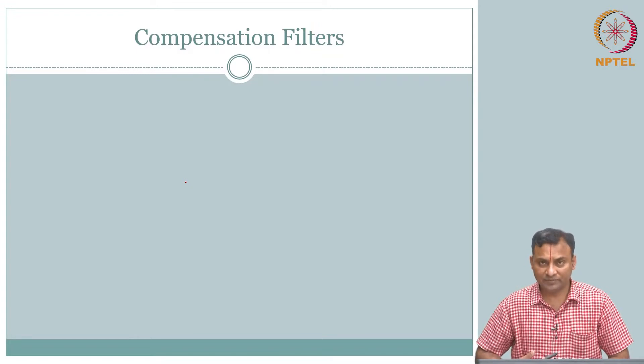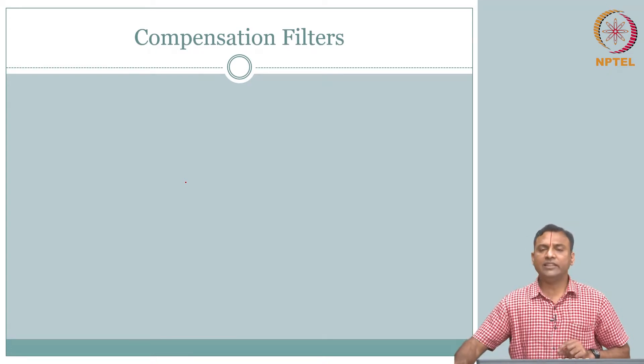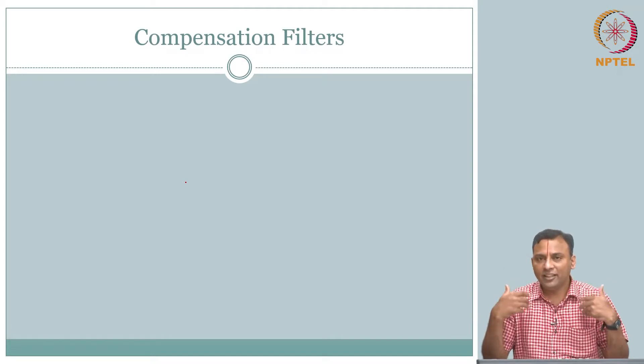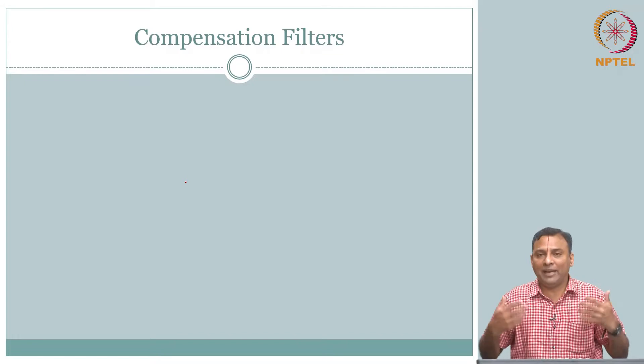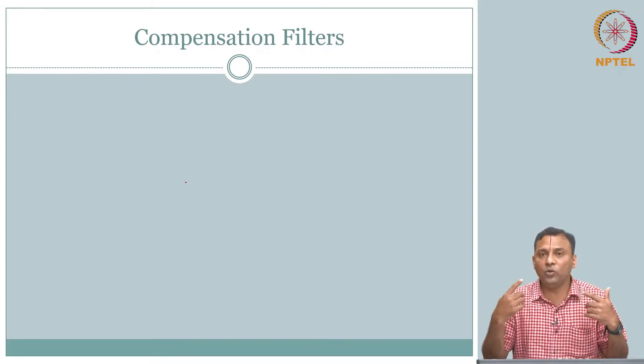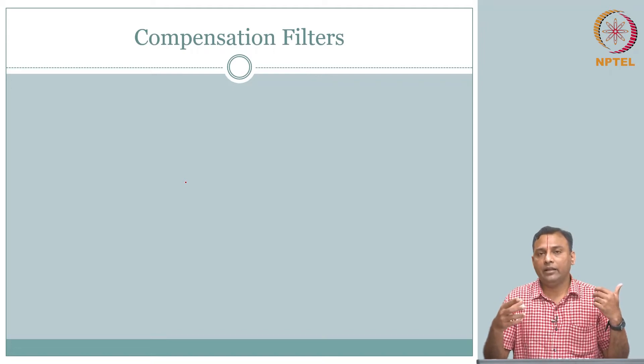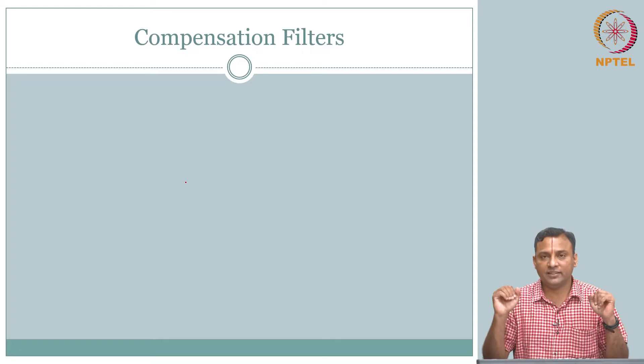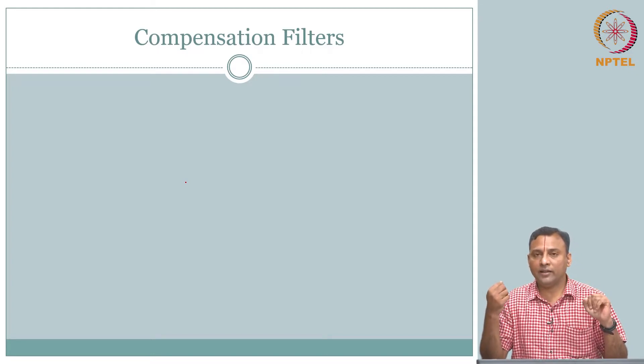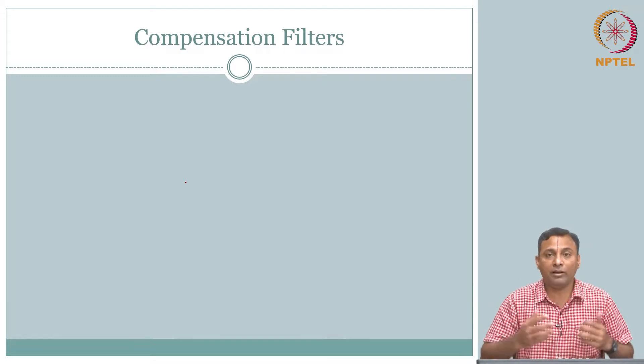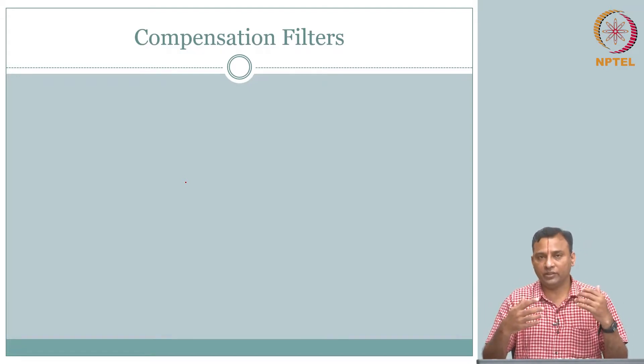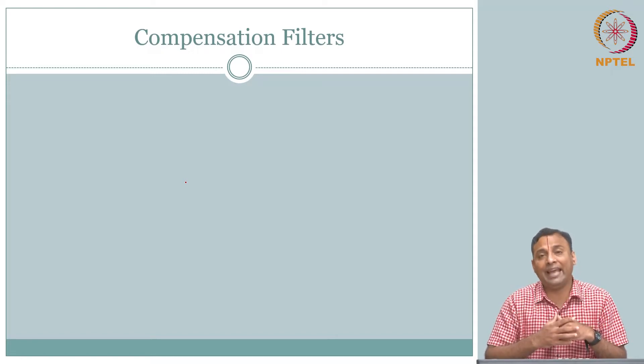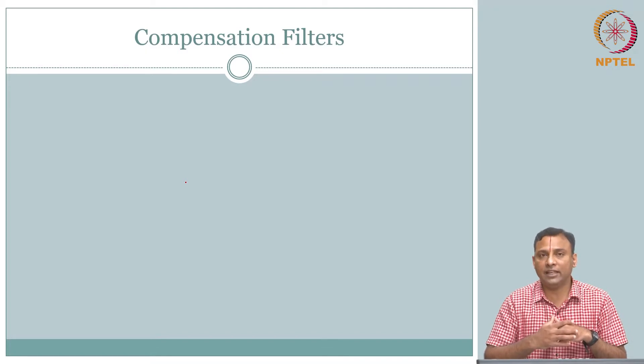What do we mean by compensation filters? This is essentially to think about: I cannot really engineer the human being — I am going to go in my native state and get an image — but what I can do is customize this instrumentation to some extent, so that the signal-to-noise ratio is good depending on the object of interest. That means if I go for a chest x-ray, or head and neck, or arm, or leg — each organ is different. So depending on which organ you are imaging, can we compensate for some losses that physics has told us about?